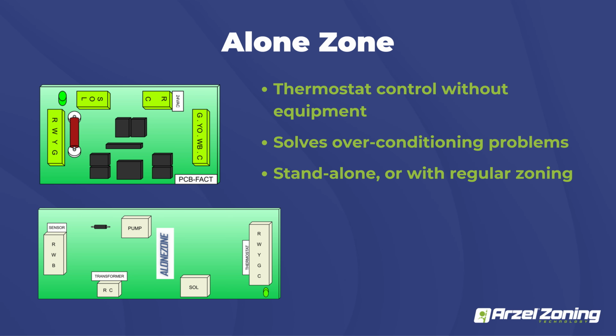So it reads voltage, not temperature based. The alone zone is a little bit more sophisticated, a little bit easier to use. It just has a sensor that goes in your ductwork. If that temperature in your ductwork matches the call from the zone that's using the alone zone, it's going to allow those dampers to open in that system.